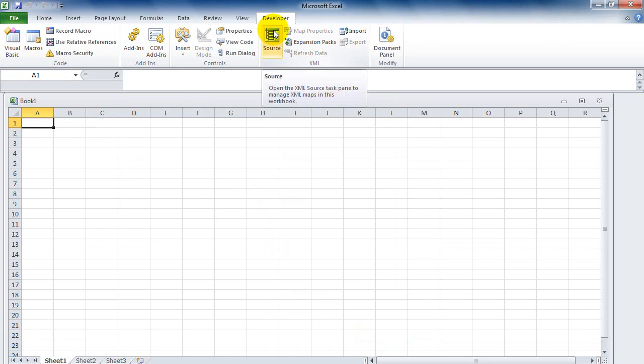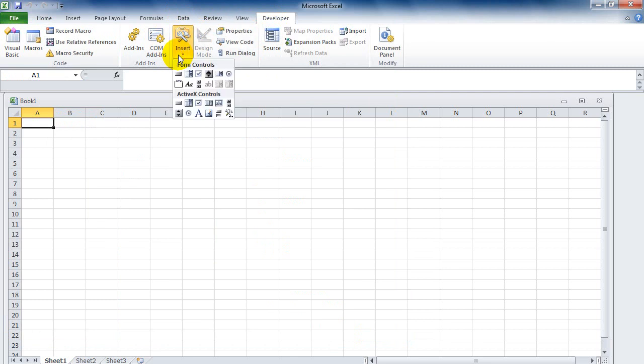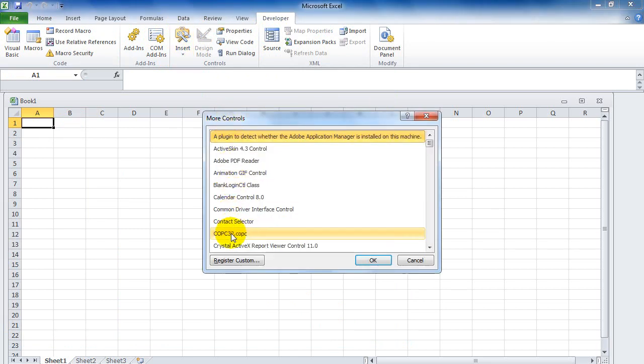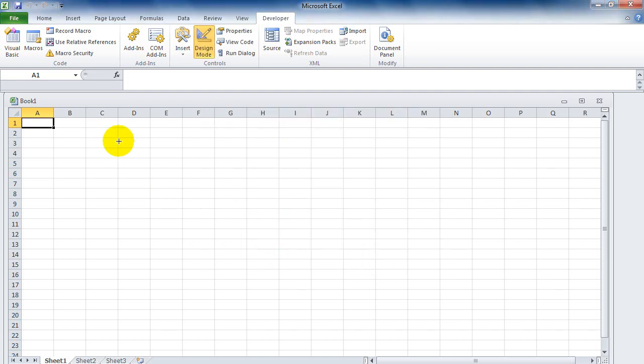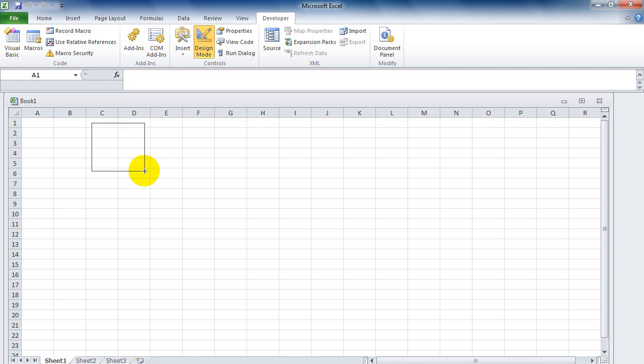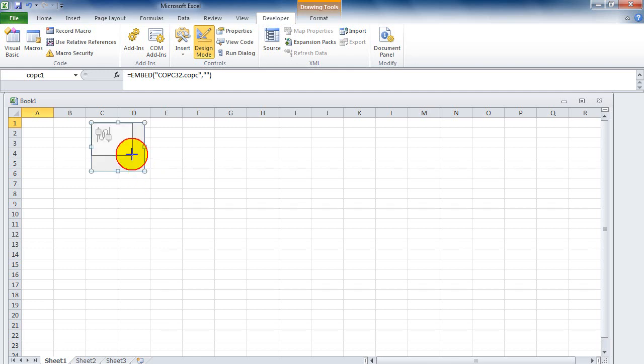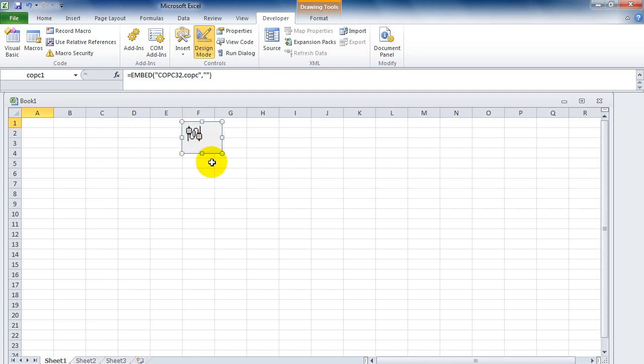First of all, you need to install COPC32 on this system. Select Insert, then More Controls. You will see COPC32 listed — this is an ActiveX control, so you need to install it first. After clicking OK, the mouse cursor will change to a plus sign, and you can drag to place the COPC control onto the sheet.